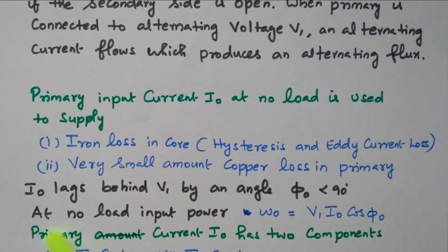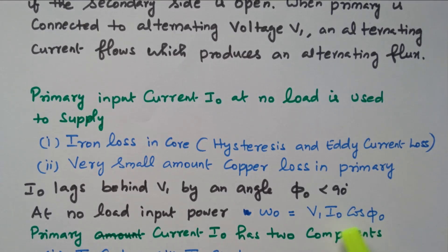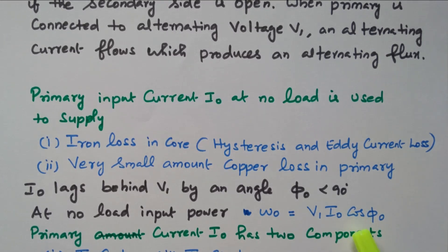At no load, the input power is W0 = V1 · I0 · cos(phi0), where V1 is the applied voltage, I0 is the small amount of current flowing through the coil, and phi0 is the angle between V1 and I0.